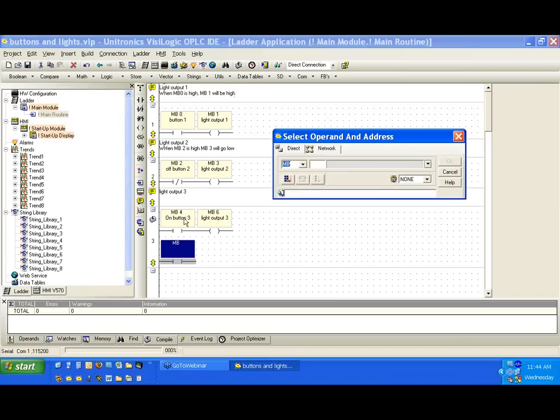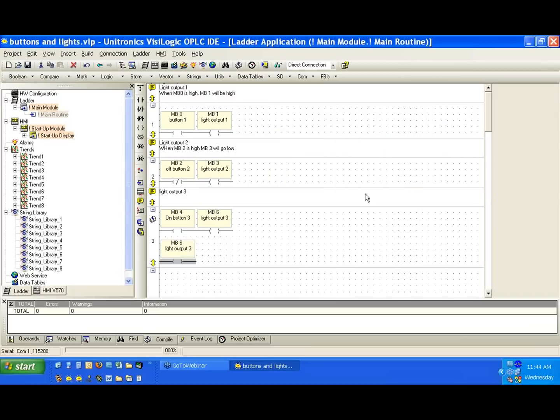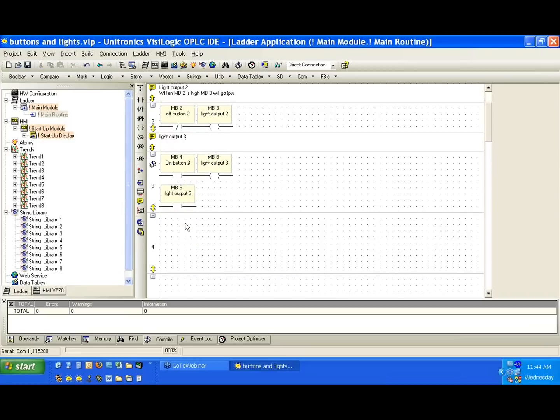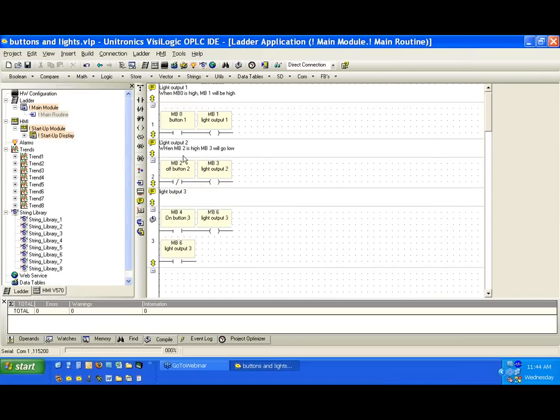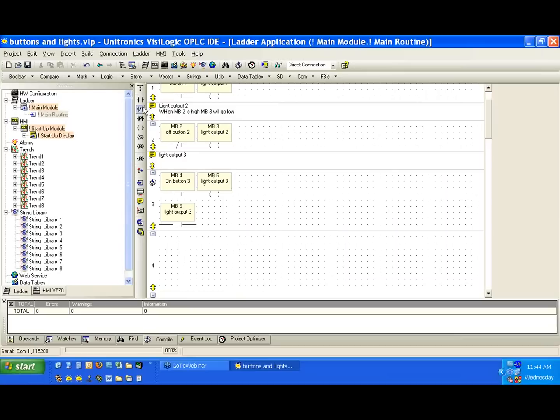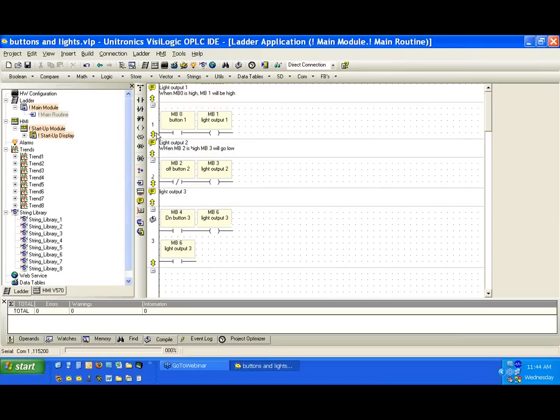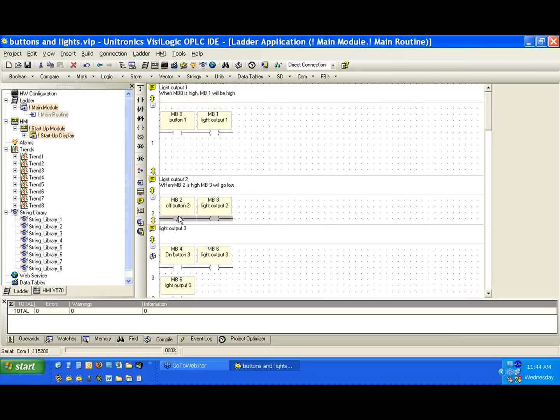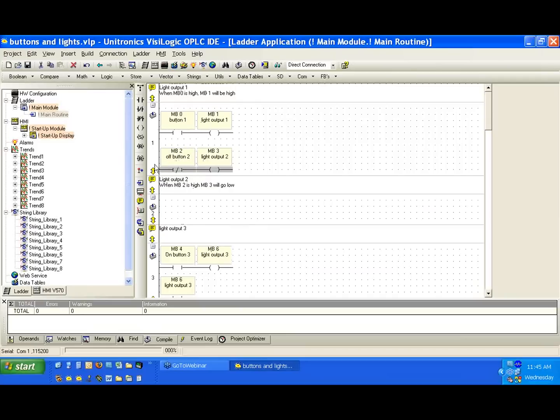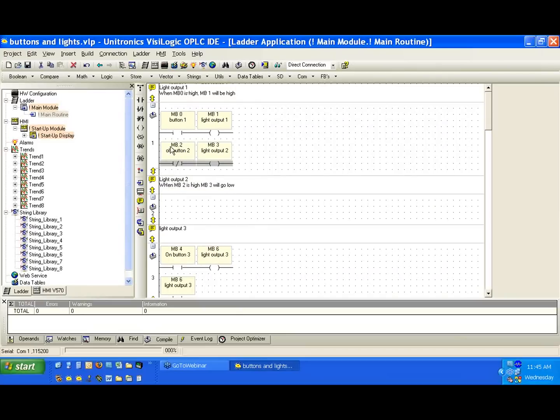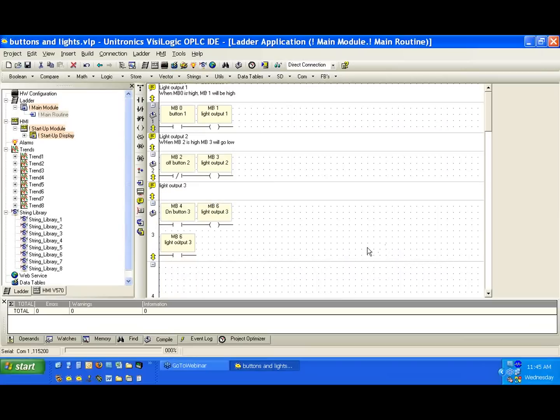So what we're going to do is place another contact right below MB4, MB6. So we're now using the coil of MB6 as the output and the contact of MB6 as an input. And we're going to connect these two elements. And I should mention that we've built three nets so far. We have one, two, three. And now we have a fourth rung starting in this net. Now, we cannot build networks that are more than one rung per net. We should try and keep all separate ideas or logic to their own net. So we have these two rungs in the same net. We don't want to see that. We want to keep them to their own network.